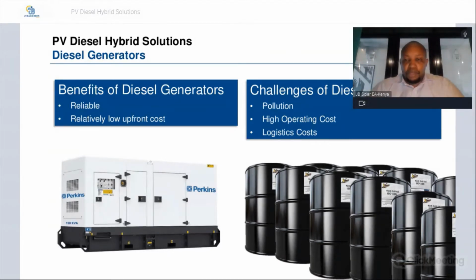So in the PV diesel hybrid solutions, we have two components. We have the diesel generator side and we have the PV solar side. So we look at the diesel generator side. What are the benefits of diesel generators? We have their reliability and their relatively low upfront costs. And generators have been used over time as backup solutions or as main power solutions in areas where there are no grids or you have fluctuations in the grid.